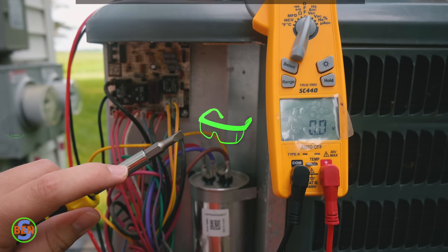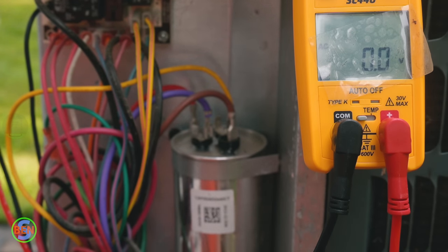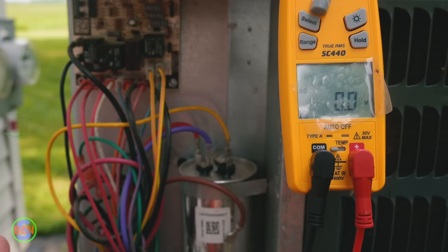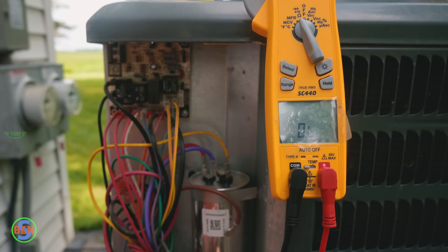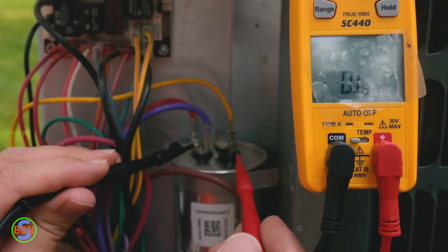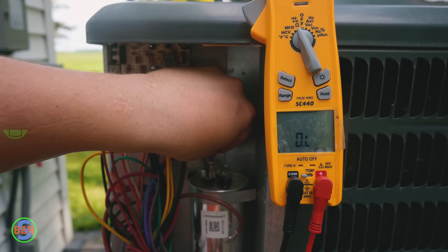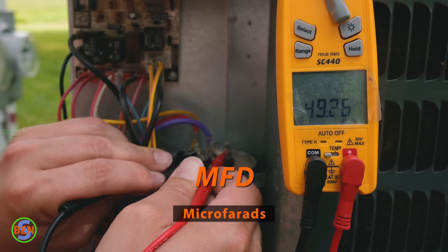Let's check right here to see if there's any voltage showing on the capacitor — there is not. We'll go ahead and short out the terminals on top of the capacitor anyway because it's best practice. Just take the metal part of our screwdriver and short it between these different leads on top to ensure we don't have any built-up electrical charge in that capacitor. We'll pull off the wire for our fan. We'll switch our electrical tester into capacitance mode — it should be able to determine what we're doing — and go from our common to the fan and see what this measures.